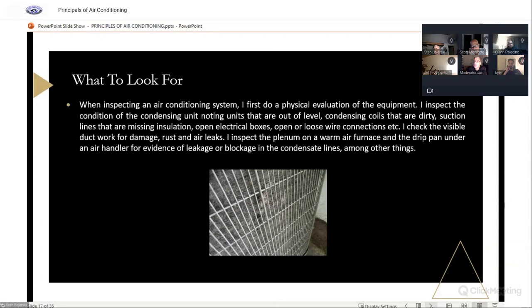But then there's the other school that says if that unit has been cockeyed for all that time, it's probably not a good idea to put it back to where it was. But I call it out anyways, and then let somebody else make a decision to say that it's fine the way it is. Coils that are dirty are going to impede the cooling process of the home. We're not going to get that hot air out of the coils properly. We're not going to send the proper pressure temperature back to the cooling coil. We're just not going to cool efficiently. Missing insulation on the suction line. Open electrical boxes. I think anybody that's been doing home inspections for any length of time probably realizes that a lot of the air conditioning guys are hacks. They may get the job done, but they don't button boxes back up.